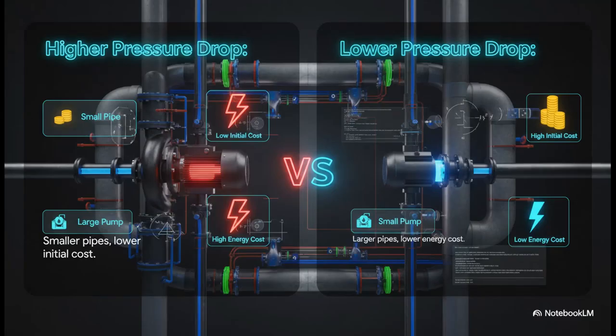And this right here is the heart of the economic decision. It all comes down to this: pay now or pay later. If you're okay with a higher pressure drop, you can use smaller, cheaper pipes right now. But you'll need a bigger, more powerful pump that will use more electricity for years and years. On the other hand, if you want lower pressure drop, you have to buy bigger, more expensive pipes up front. The payoff? You can use a smaller, way more efficient pump that saves a ton on energy bills over the long haul. It's that classic battle: initial cost versus lifetime cost.